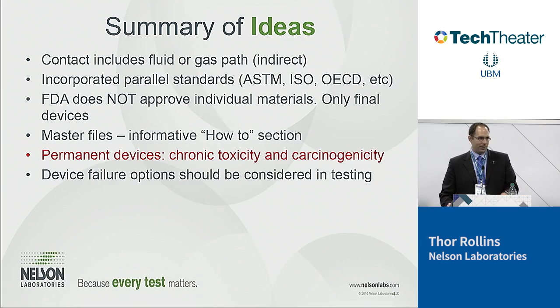Don't let a $170 test ruin your device. Let's look at it. Let's investigate why it failed. Let's determine if it's a true risk or not. Remember, a lot of these tests are screening tests, trying to determine the risk. And just because you failed doesn't mean that that is a true risk to the patient. We need to determine that. So if you do fail, contact your lab, let's talk through it, determine why you failed, and determine if it's a real risk to the patient or not, okay?